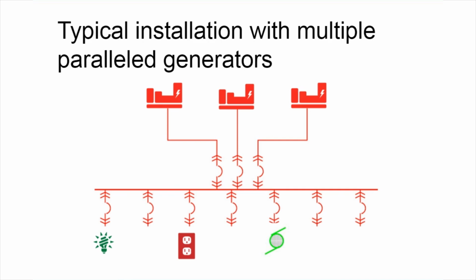Another option with this type of installation is to use that +1 generator to pick up a little bit more of your site load on your generator system. And as long as you can shed that load in the case of a failure of a generator, and still maintain your more critical life safety loads, you can add a lot more power onto the system and give the owner a lot more flexibility.